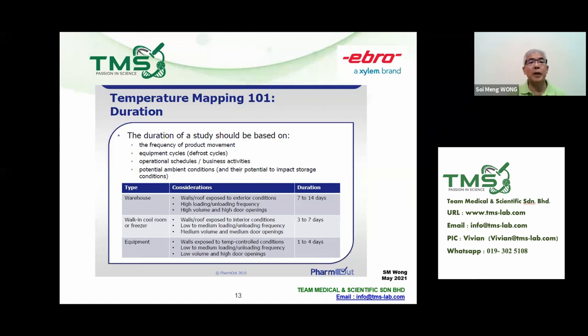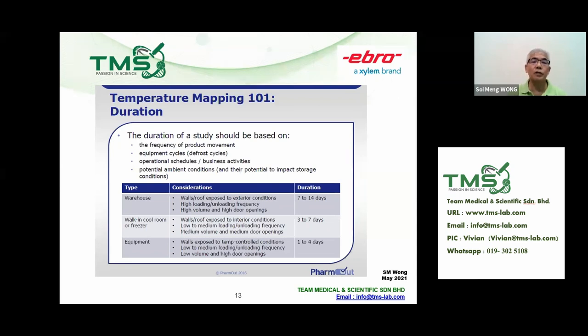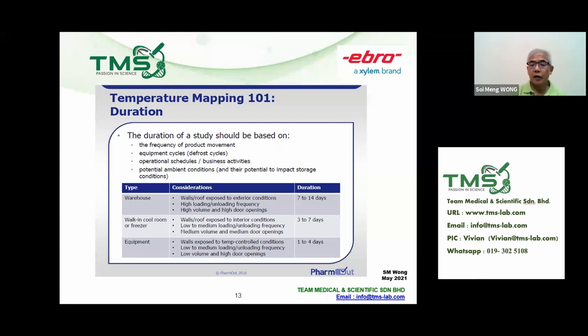The duration also depends on the operation schedule, business activity, potential ambient conditions, and their potential impact on storage conditions. If your warehouse faces the sun and the wall is poorly insulated, it will affect the inside temperature. The recommendation is seven to fourteen days for a warehouse, three to seven days for a walk-in cold room or freezer, and one to four days for equipment such as a refrigerator or freezer.